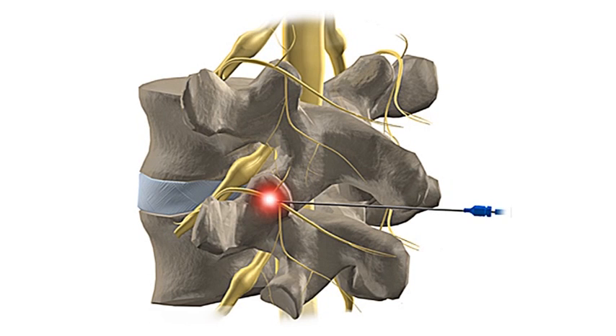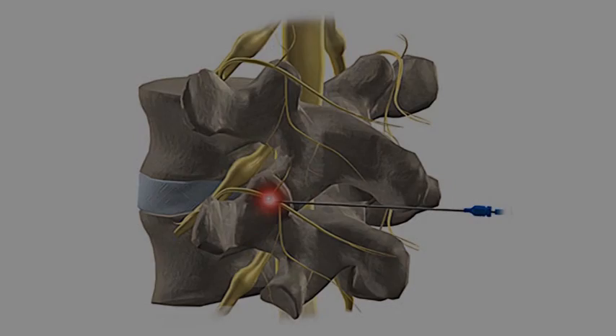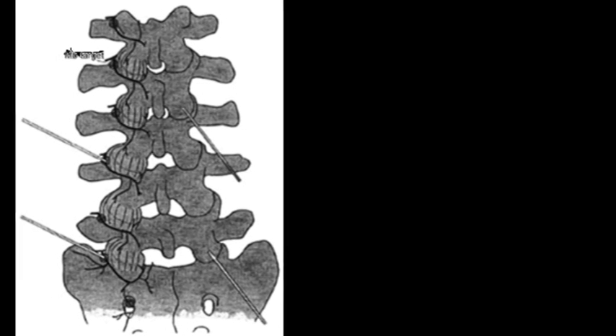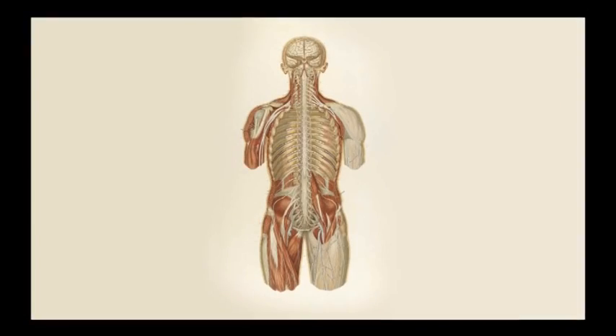About 15 years ago, Swiss and Dutch pain therapists noticed that the temperature is probably not solely decisive for the thermal lesion, but that the electric field thus applied to the nerve influences the therapy mechanism positively and contributes to the effectiveness. With the stiff electrodes used in the past, it was not possible to reach the spinal canal, and it was very difficult to accurately locate the nerve pathways.